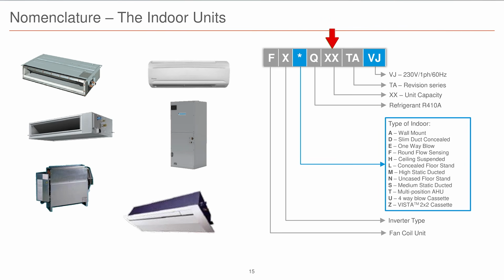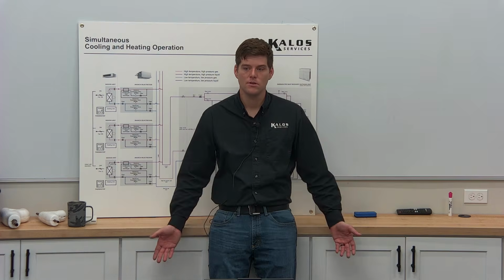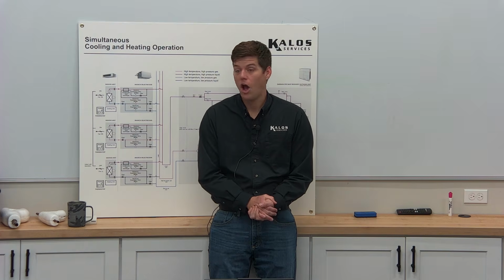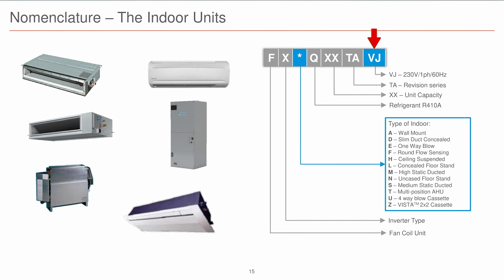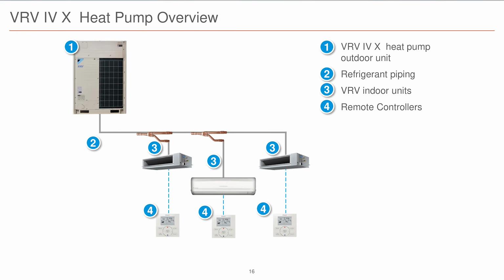If it's an FXMQ36, what does that mean? It's 3 ton, 36,000 BTUs, at 12,000 BTUs per ton. They're always going to be divisible by 12. And then you'll notice the VJ at the end. All the indoor units are 230 single phase, or 208 single phase. It's the outdoor units where you get into the weird voltages of 460. That's all the letters; they all mean something, right?